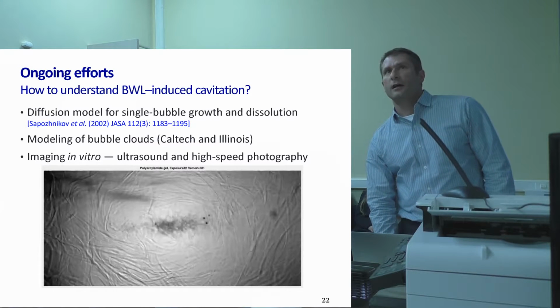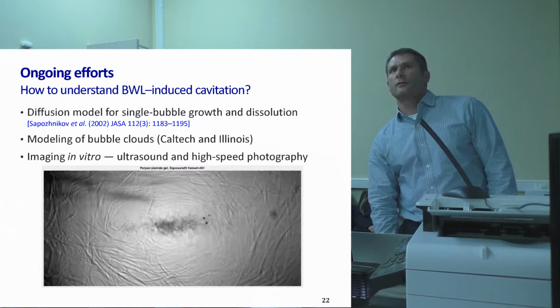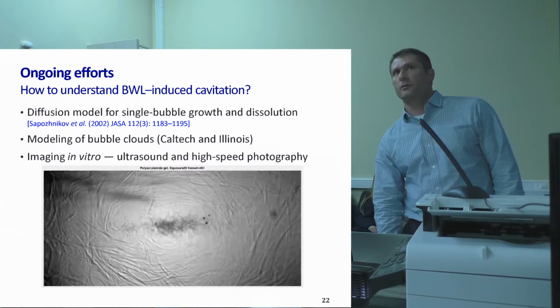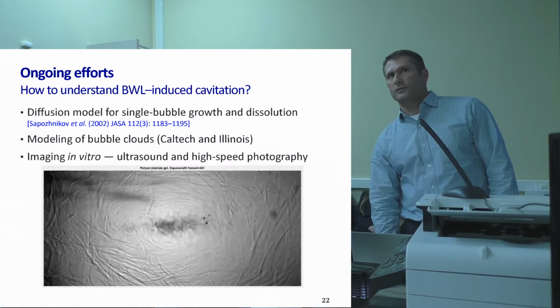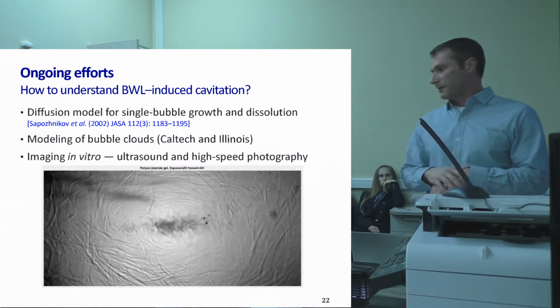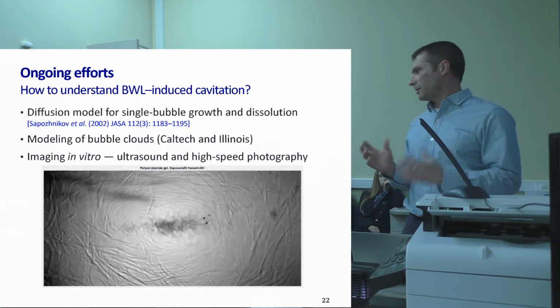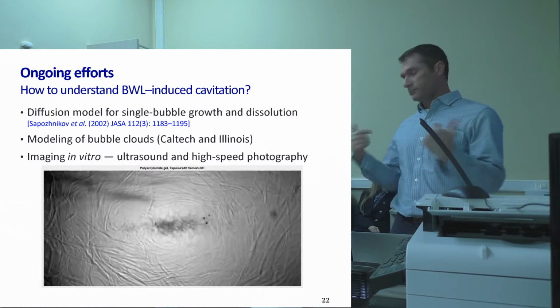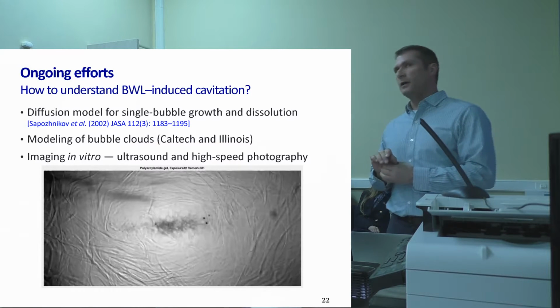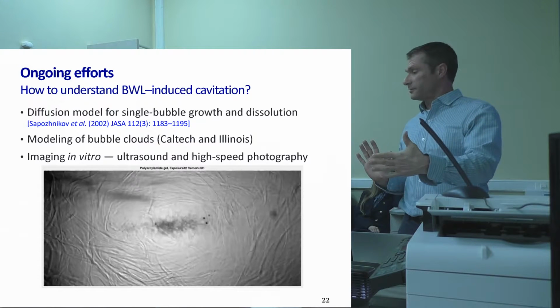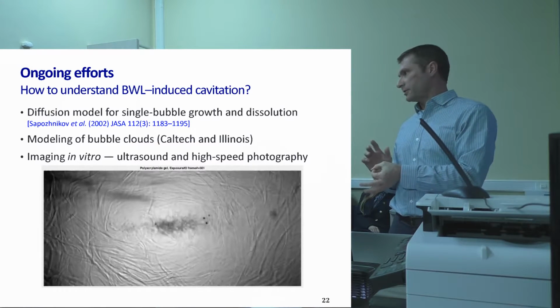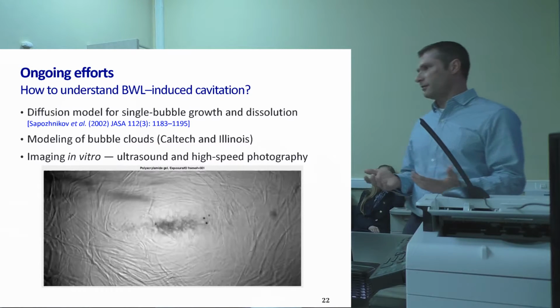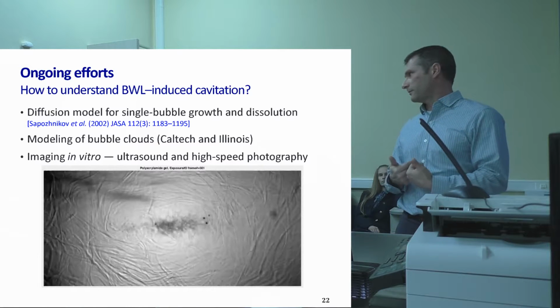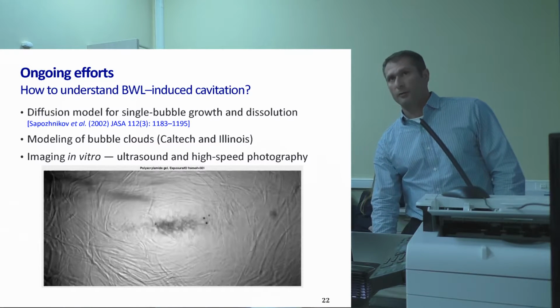So ongoing things that I'm interested in are how we are going to understand the BWL-induced cavitation. One thing would be a simple diffusion model. This mimics a paper that Oleg and Vera and others in the PPG group worked on a number of years ago, which was simply if you have a single bubble, you can calculate during the dynamic part of its excitation how much non-condensable gas diffuses into the bubble. Then in between, while it's quiescent, so there's no acoustics applied, the bubble should just be sitting there, slowly dissolving. You can calculate how fast it dissolves and whether bubbles that you excite in one pulse should be around for the next pulse. That's a simple thing that we can do, and we've already done some of those calculations.